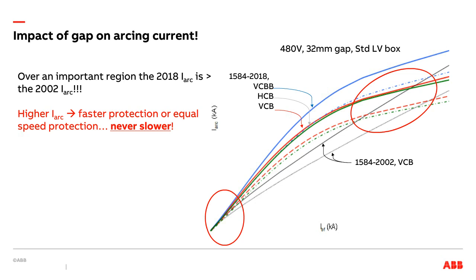That's a horizontal, that IBF at the bottom there, and you look at the arcing current as the vertical axis, you'll see that those colored lines are generally above the black line. Those color lines are curved, they have a little belly to them, they're convex, and the black line is kind of a straight line. And for most of the range of current, the color lines are above the black line. Notice that to the right, where I have the little red egg, that's no longer true. For some scenarios, the arcing current in the new model will become lower.